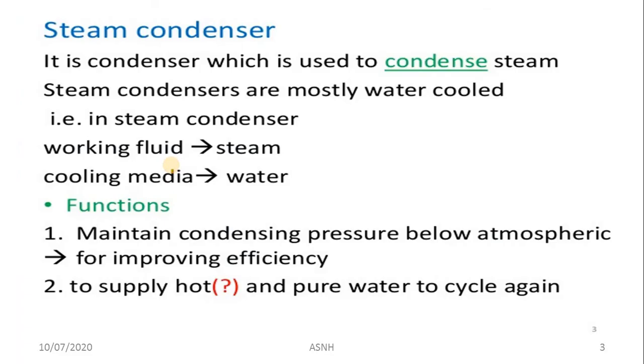Now in this slide we will discuss what a condenser is and what the function of the condenser is. So a condenser is generally a closed shell. It is made by some kind of fabrication process, and a vacuum needs to be maintained inside the condenser shell in order to produce a good condensate. So vacuum is very important in the condenser shell.